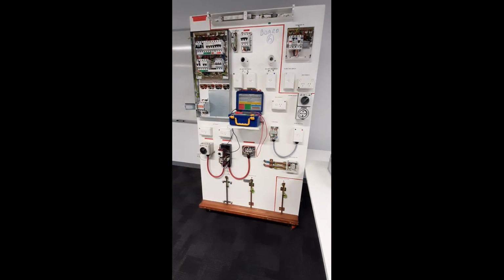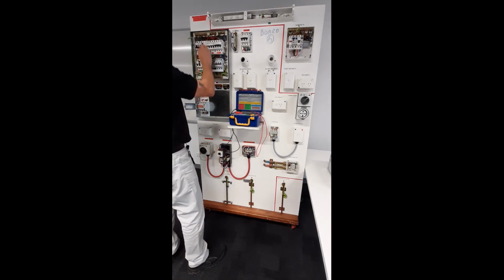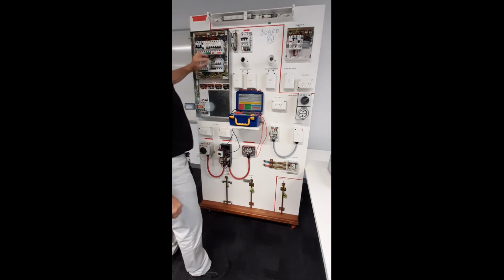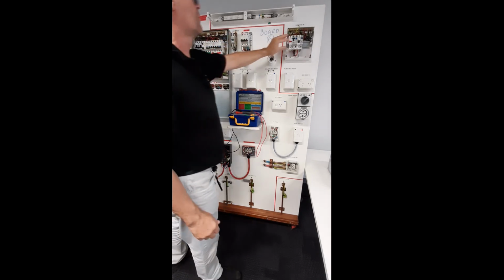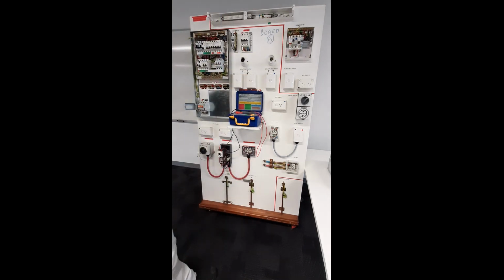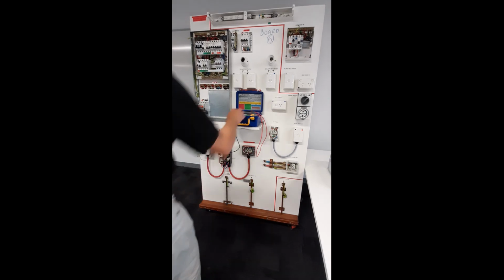A result of less than 1 megaohm on the whole installation means that you must test each circuit individually to locate the circuit with the fault. Turn every main switch, circuit breaker and RCD off. Test each active to earth and each neutral to earth separately.